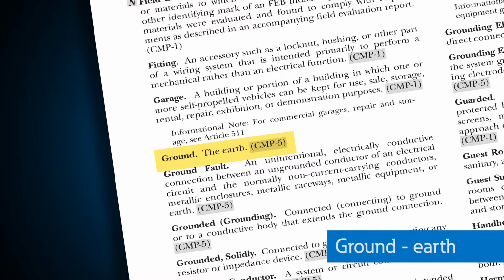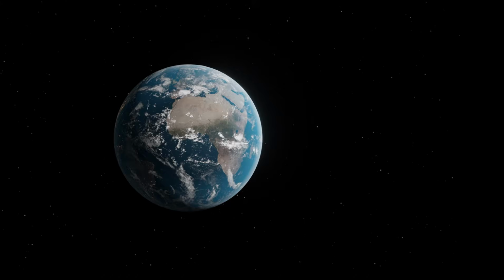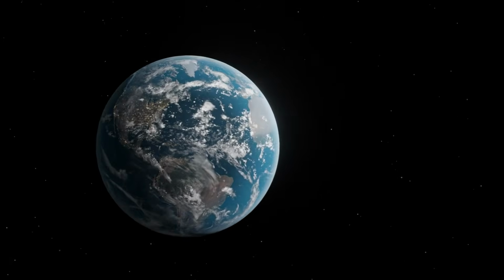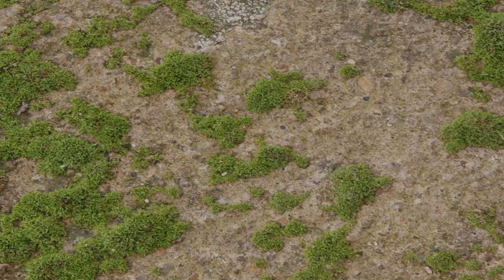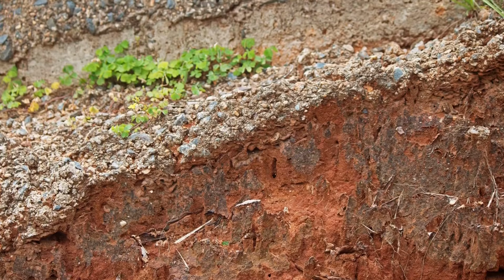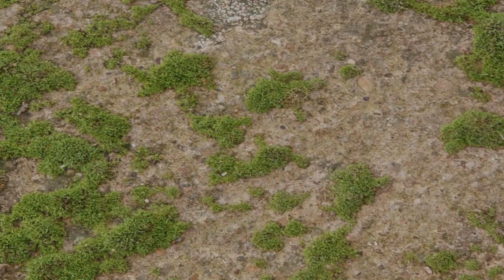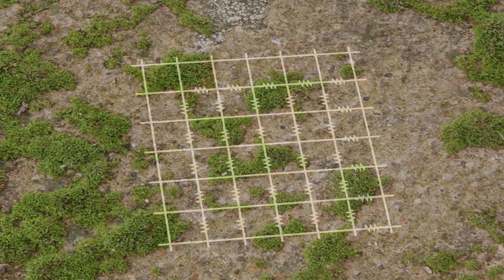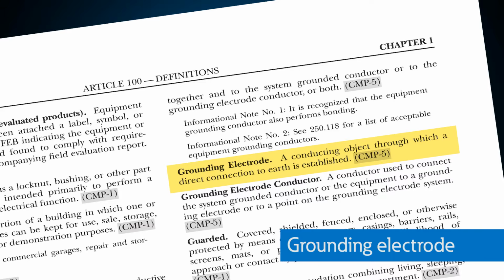The National Electrical Code tells us that ground is the earth. I think it's the shortest definition in the National Electrical Code. We define ground as the earth. So anywhere you use the word ground, you're thinking you're tying to or connecting to the earth. Because the earth does not come with terminals, we have to establish a connection to earth, and we do that through what we call the grounding electrode.